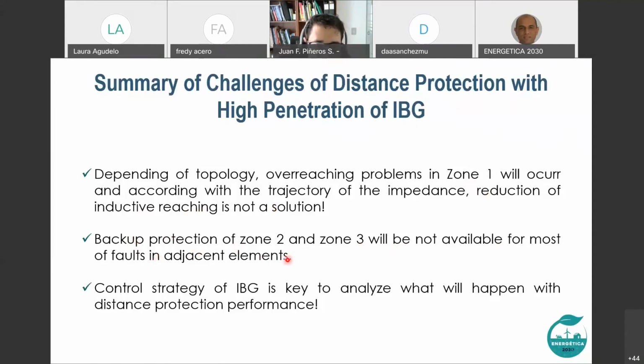This is important. Then we have to think about how we will provide a backup, because, important to say, if we don't provide a backup properly, it could be that the inverter-based generation will disconnect because of low voltage ride-through. And this is very important, and we have to care about it, because if you remove, for example, 1,000 megawatts of power because you have a failure and you cannot provide a backup, then you will have a big consequence and maybe a major blackout in this case.